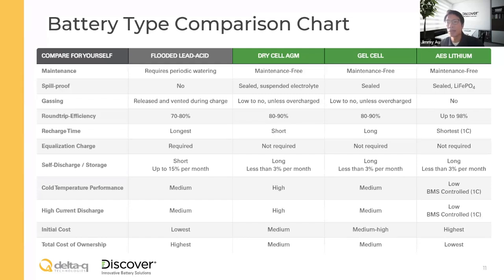With a flooded battery, the cost to produce it is lower compared to the other technologies, so the initial cost is the lowest. But if you factor in total cost of ownership—the labor and time required to top up with water, check water levels, perform equalization, and clean terminals due to potential corrosion from off-gassing—those are costs you don't see upfront. So total cost of ownership tends to be higher for flooded batteries.